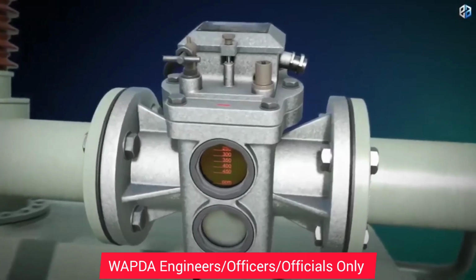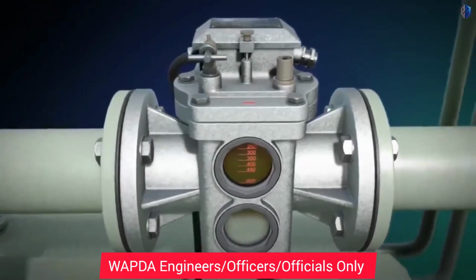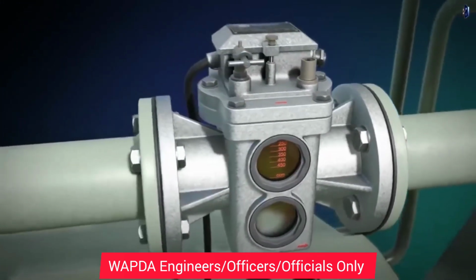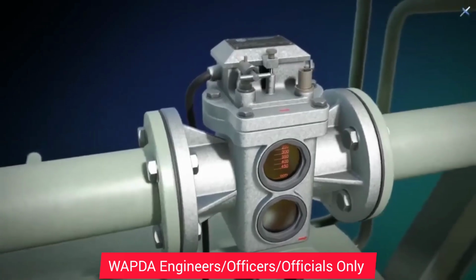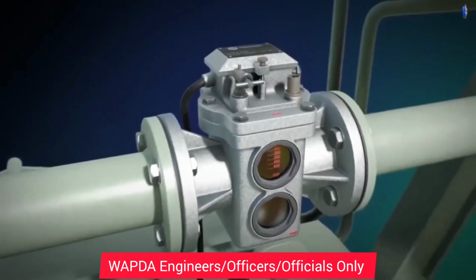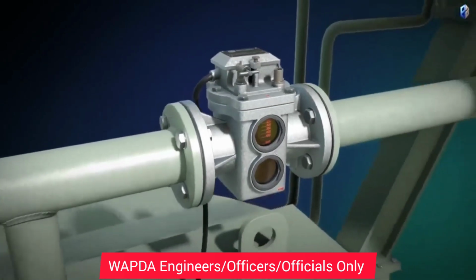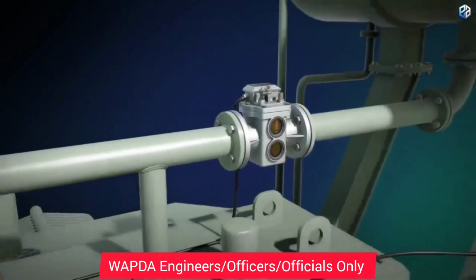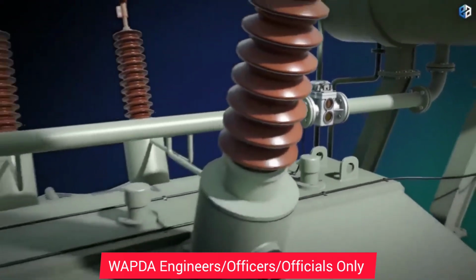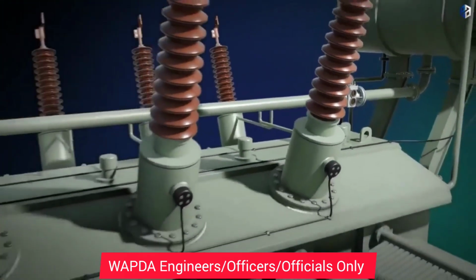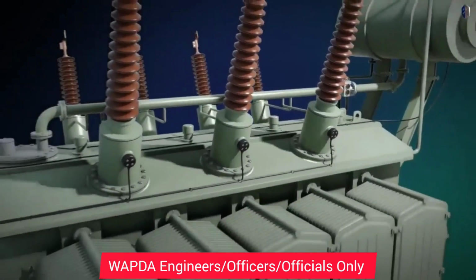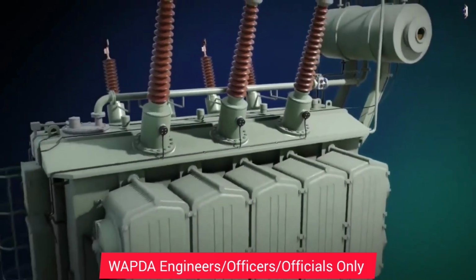The Buchholz relay is a small but crucial component for protecting large transformers. It detects problems at an early stage, and in an emergency, it disconnects the transformer from the grid at lightning speed and at all poles.